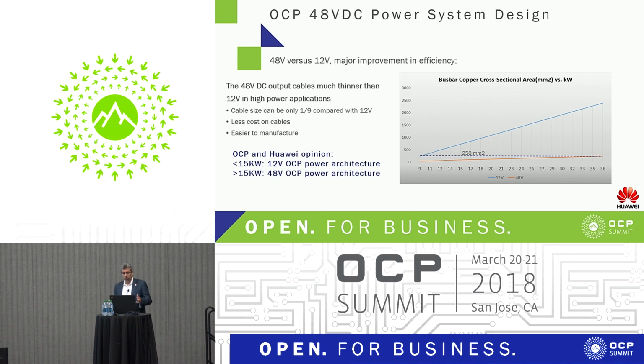We think we can probably make it work in the 10, 12, 15 kilowatt range for 12 volt. Once you get above the 15 kilowatt range, you really should consider 48 volt. This is important, maybe even more important for manufacturers of equipment like servers to consider, because you may focus on your one server and think, we're using 50% more power, that's not too bad—and for one product it's not. But get 10 or 20 of these in a rack, and it becomes very significant.